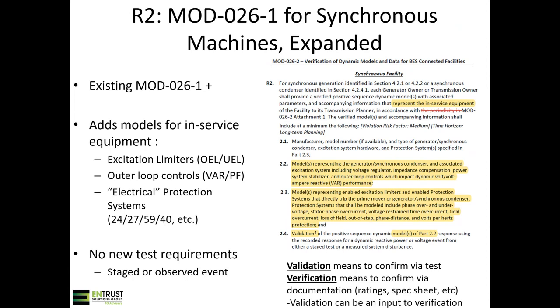As someone who does modeling day to day, I can say that's definitely not best practice, but there's a difference between best practice and what NERC is requiring of you. There are definitely circumstances where you'd want to do much more than just a step test, but that's not what the standard requires. For verification—all these limiter models, outer control loops, protection systems—the requirement is only to verify them.